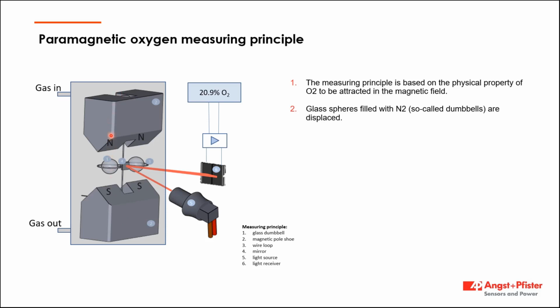In between this magnetic field, where we want the oxygen to be concentrated, we place two glass spheres filled with nitrogen, the so-called dumbbells. They are suspended with a very thin wire, and there is a small mirror attached to this dumbbell. As soon as there is a concentration of oxygen, it comes to a deflection of this dumbbell, which also causes a deflection of this mirror. With a light source projected onto the small mirror, and then reflected to a positioning photodiode, the deflection can be measured.